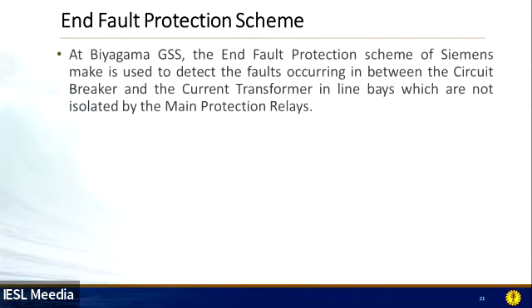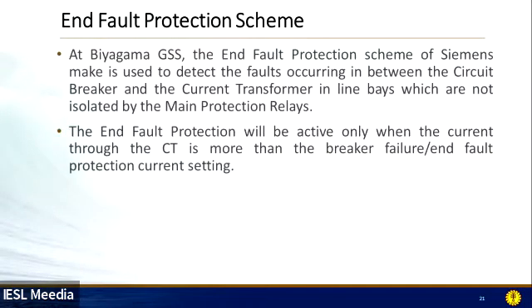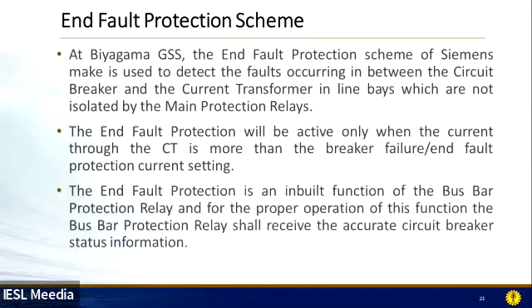Next, the end fault protection scheme. At the Biagama grid substation, the end fault protection scheme of Siemens make is used to detect faults occurring between the circuit breaker and the current transformer in the line bay, which are not isolated by the main protection relays. The end fault protection will be active only when the current through the CT is more than the breaker failure end fault protection current setting. The end fault protection is an inbuilt function of the busbar protection relay, and for proper operation of this function, the busbar protection relay shall receive accurate circuit breaker status information.